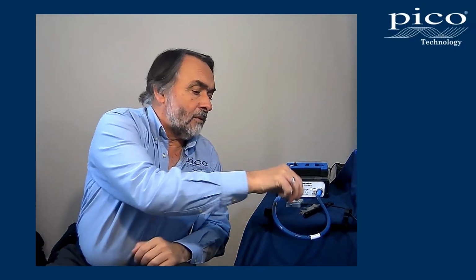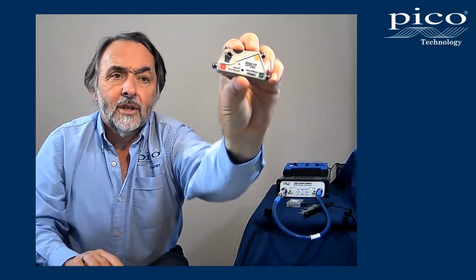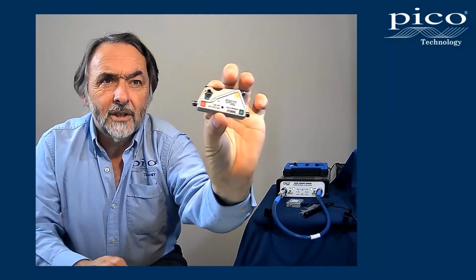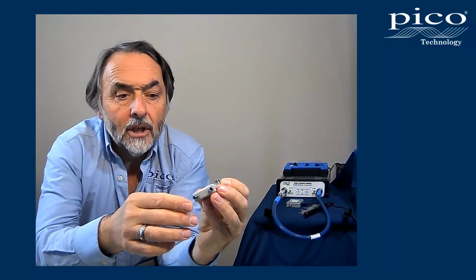Okay, so that was a fairly compelling demonstration of the quality of the e-calibration against a manual calibration. But we should go a little bit further. When we make one of these a manual fixed calibration piece, we can realize a fairly good short simply by placing a hard short at the end of a transmission line inside the device here. Likewise, we can realize a fairly good open by putting a low fringing and low capacitance open at the end of a transmission line in here.